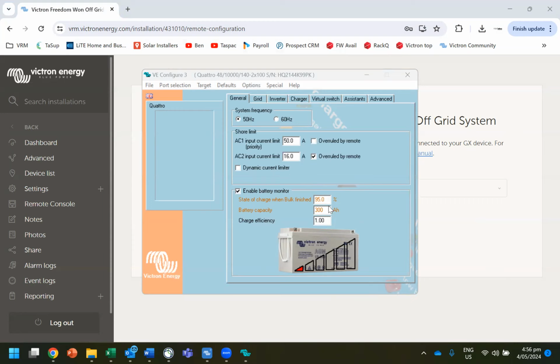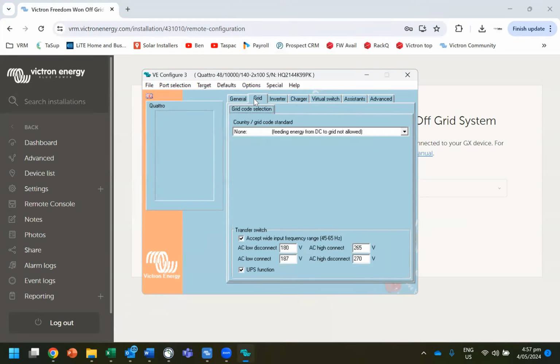Okay, so this setting here, the battery state of charge, is not going to be calculated by this. The only time that it is going to be calculated by these settings is when the battery communications cable gets disconnected, and then the Freedom Won battery can run standalone. It's perfectly capable of that. So these settings then come into play, and the Victron system starts calculating the state of charge, etc.